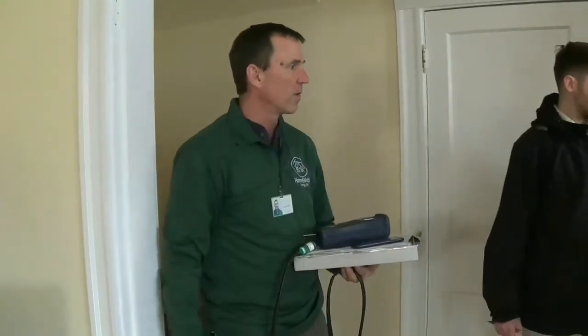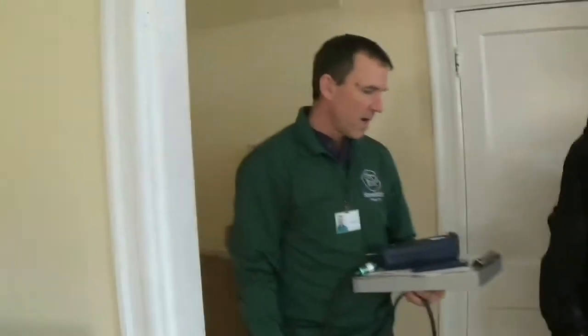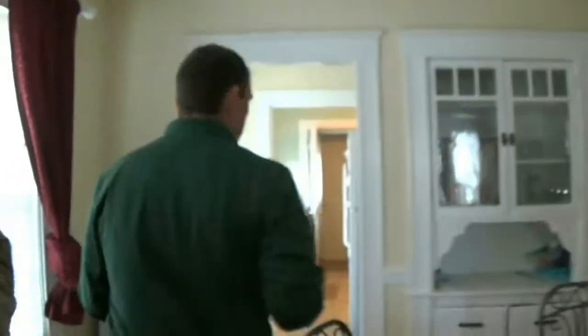And now is where I would usually get the homeowner to help me by closing any windows and doors that are currently open. We've already checked and all the windows are closed, but we're going to close that front door behind us. And now we're going to make our way to the thermostat. We're going to note what temperature it was set for. We set it 63. I'll write that down. And then I'm going to crank this thing way up, and I'm going to immediately walk down to the basement, and I'm going to find the system switch to disable it.